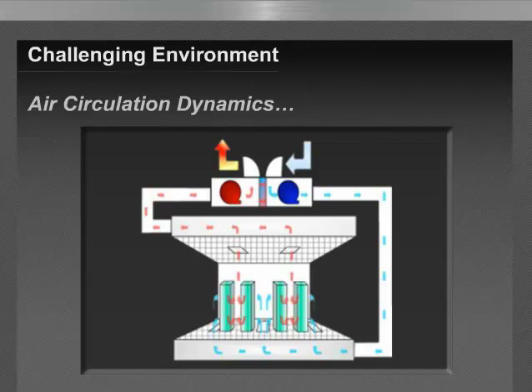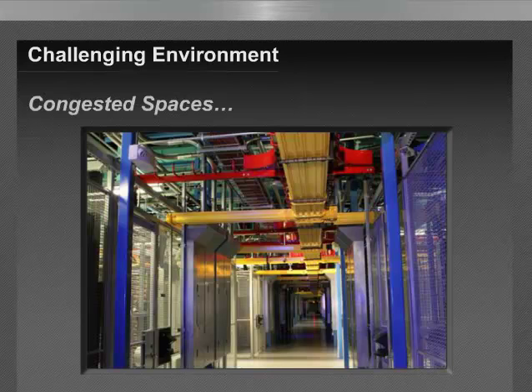Next on our list is congestion, congested spaces. As we look at fully or partially enclosed cabinets and structures, loaded cable trays, process piping, ductwork, and other obstructions, they all impede smoke delivery to conventional passive spot-type detectors that might reside at the ceiling. So imagine in this installation you have your smoke detector at the ceiling, with fully loaded cable trays, process piping, ductwork, and all the other things that go on the ceiling. We start to think about smoke delivery. Smoke actually getting past the obstructions can be expected to be impeded.